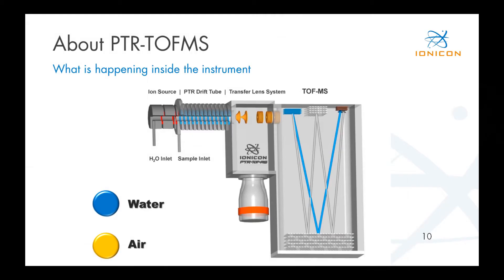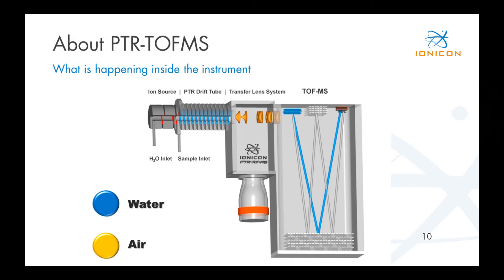Now that we are back from the lab, I want to give you some information about what's happening inside the instrument. In our instrument, at first we have an ion source — it's a hollow cathode ion source. This means you have a plasma burning inside and you have an inlet for water vapor. Down here there is a reservoir filled with liquid water that is constantly evaporated into the source. Because of the sophisticated design of the ion source, the H2O is very efficiently transferred into H3O+, meaning it gets an additional proton attached.